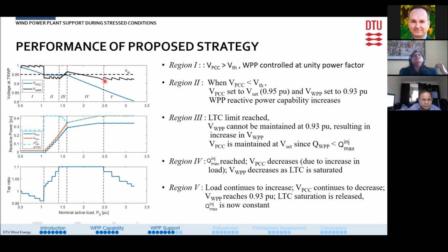As a result, the wind power plant voltage now reaches 0.93, which was the set voltage from our proposed control strategy. When the wind power plant voltage reaches 0.93, the tap changer limit is released. The taps are no longer saturated, the reactive power capability now becomes constant, and the voltage at the wind power plant is maintained at the set voltage.